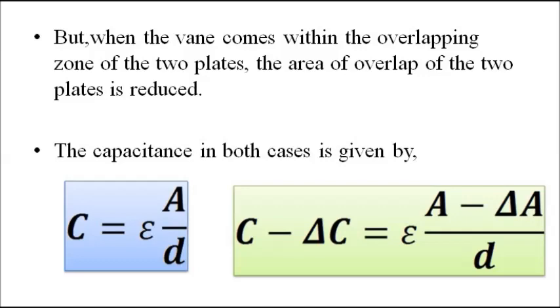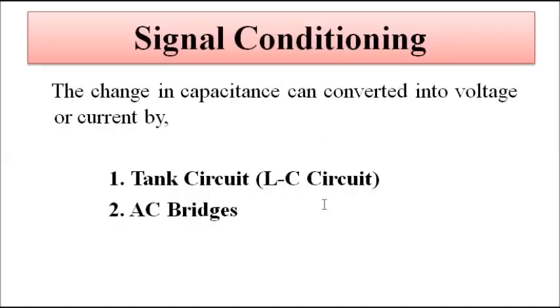To convert this change in capacitance into a suitable voltage, we have to use a signal conditioning circuit. This signal conditioning can be in the form of a tank circuit — an inductor-capacitor (LC) circuit — or we can use AC bridges involving capacitance. So the signal conditioning mechanism can either be a tank circuit or an AC capacitance bridge to convert it into a suitable voltage or current signal.